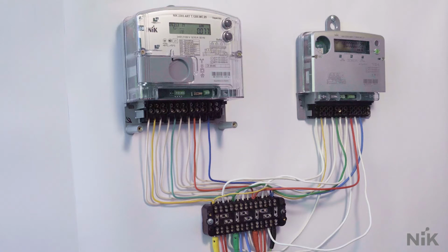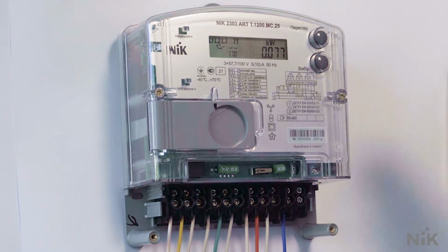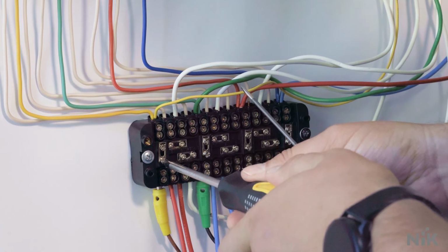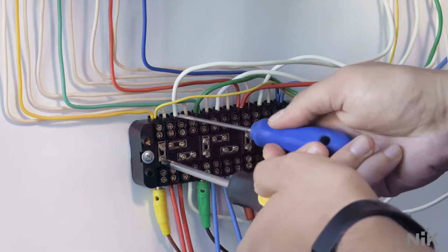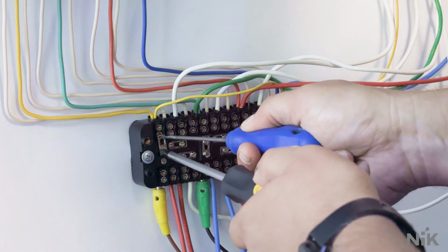We have disconnected the load from the meter by disconnection of the jumpers. We disconnected the load of current circuit from the metering device by connecting of 3 jumpers. The device has no load. Now let's move to the second stage, disconnection of voltage from the device in order to dismantle the device safely.